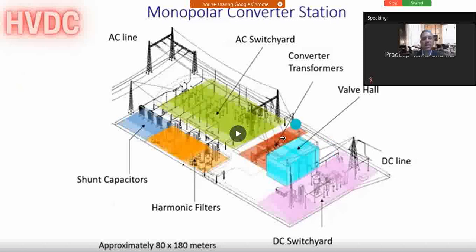There is another technology, capacitor commutated converter technology, that is CCC HVDC. So that is also one of the developments in HVDC, where between the converter transformers and thyristor valves there is a series addition of additional series capacitors for the reactive power support of the DC link.